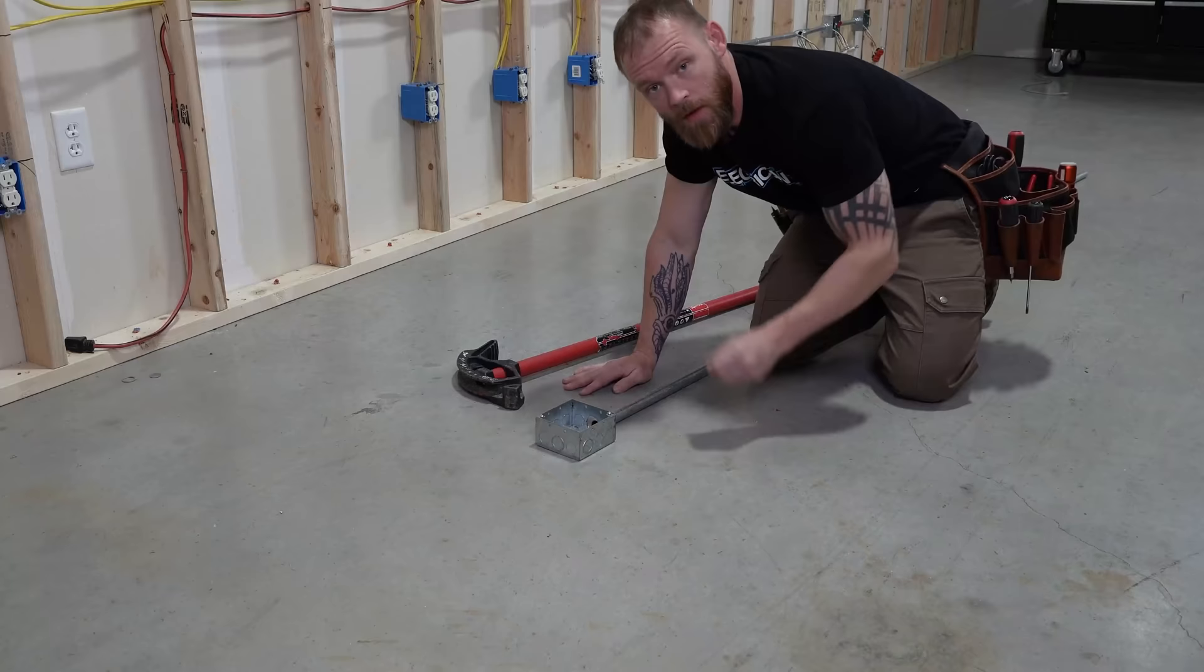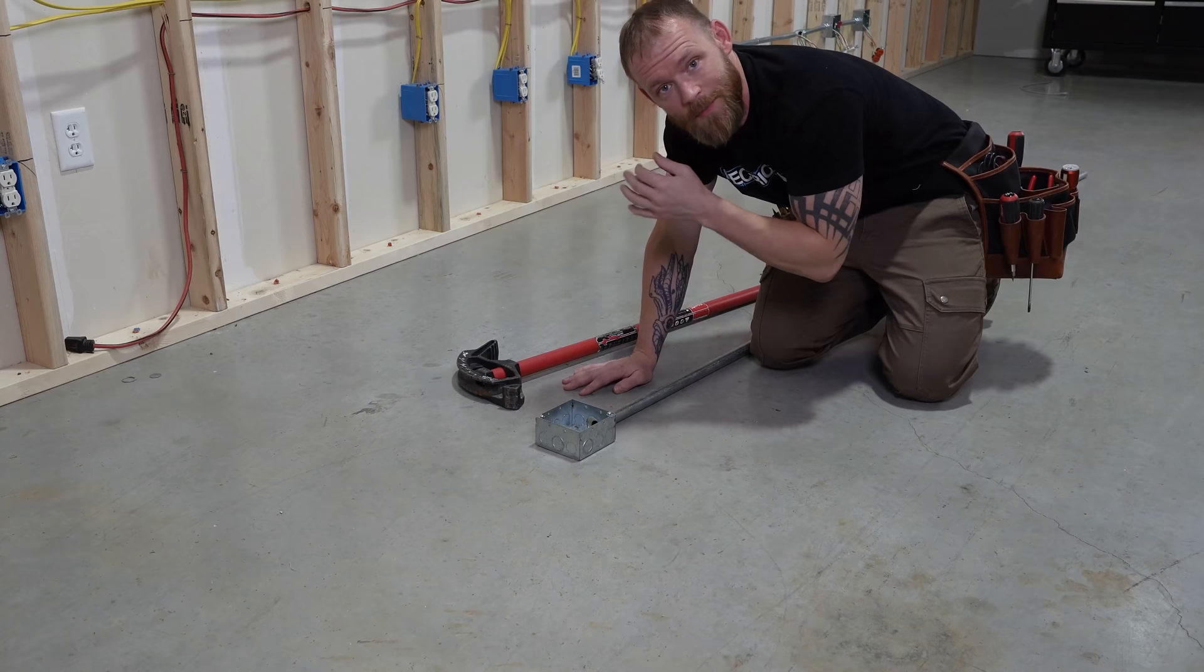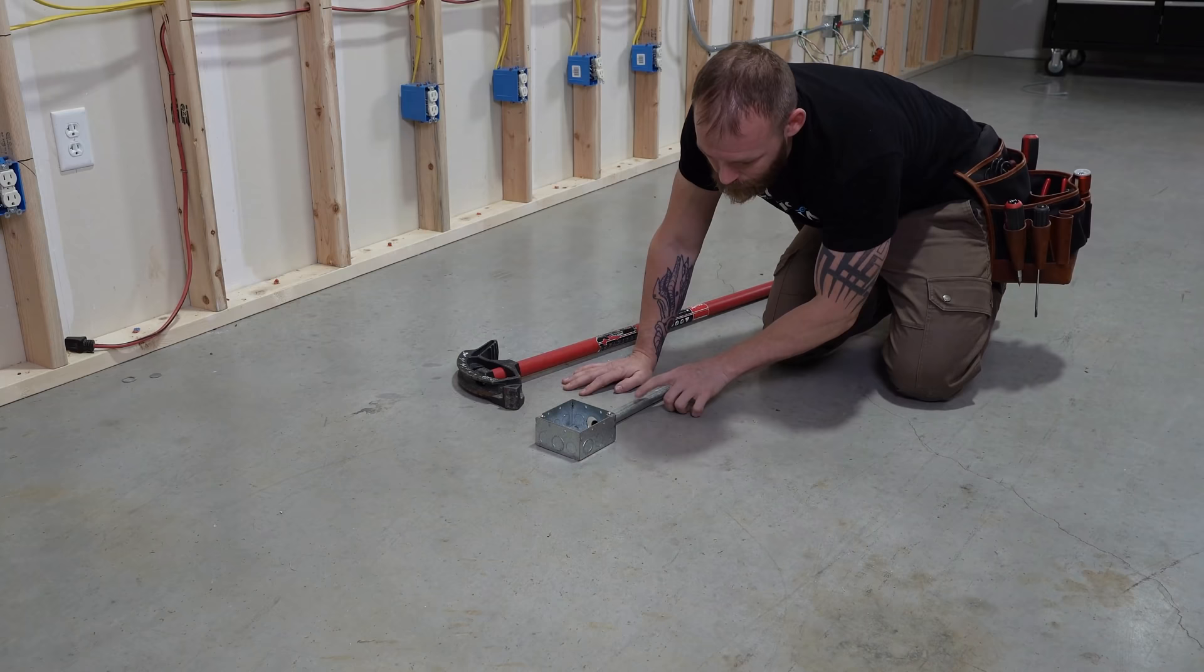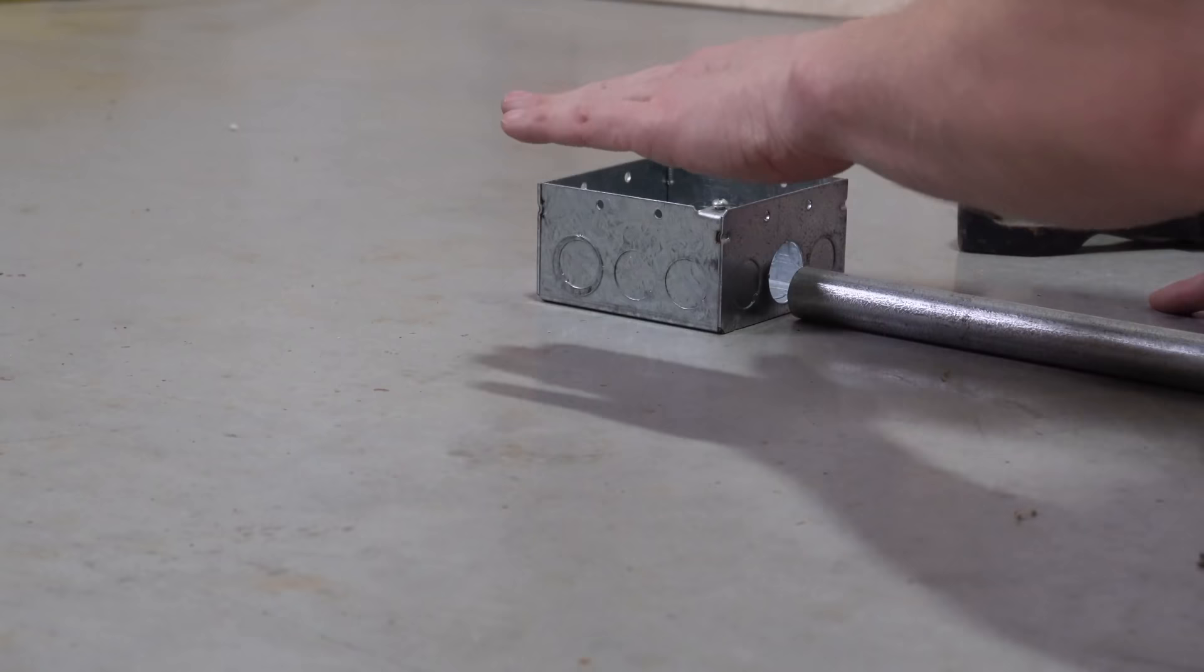All right, so out in the field every once in a while we run across something we have to do called a box offset. A box offset is essentially bending a piece of conduit in a way, kind of making an S-curve on it, to get into something that is raised.